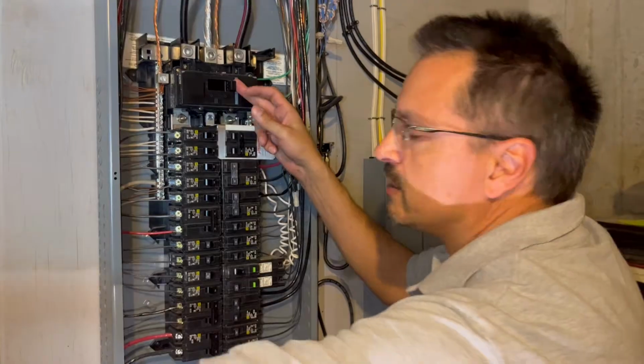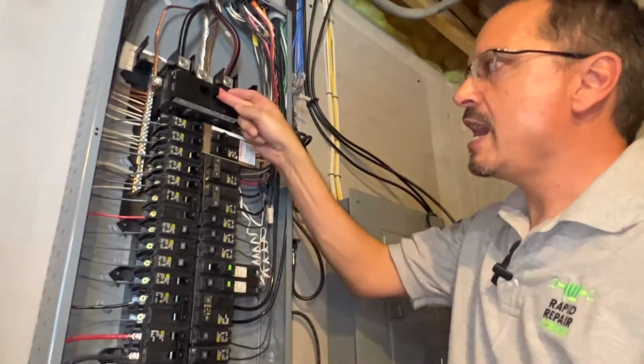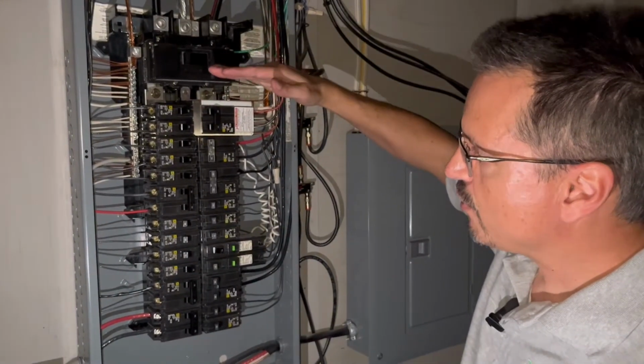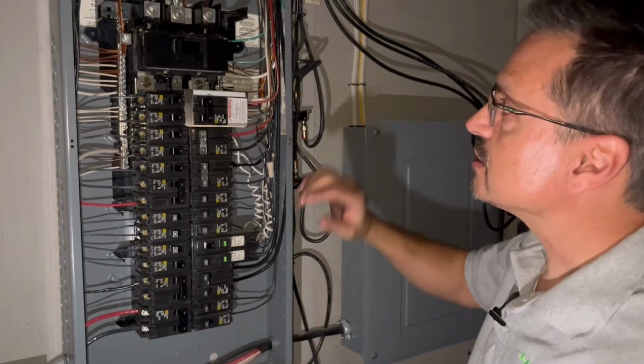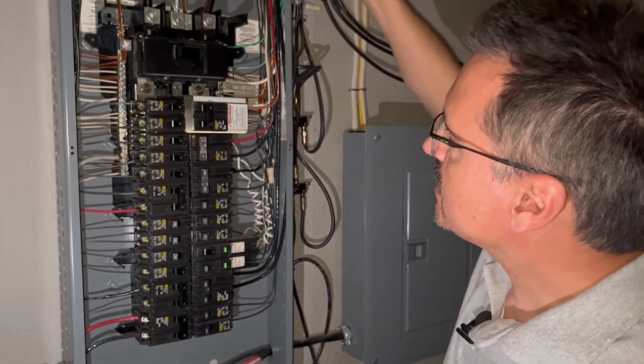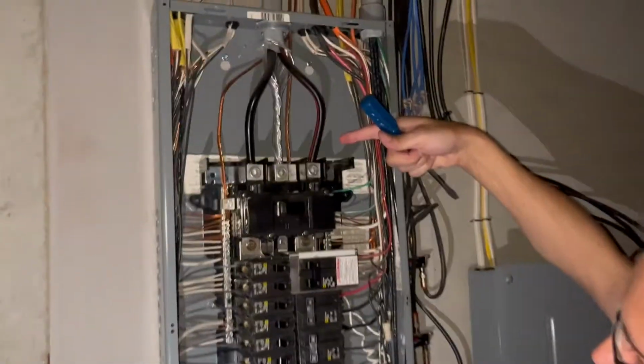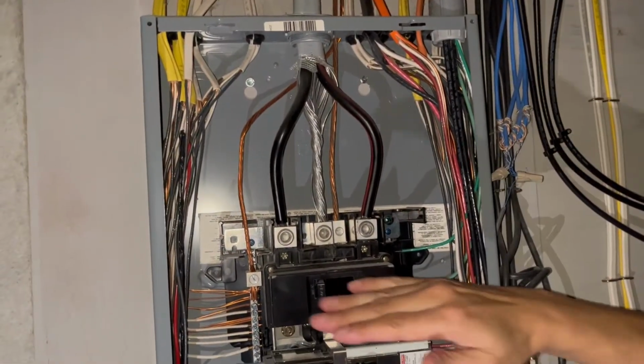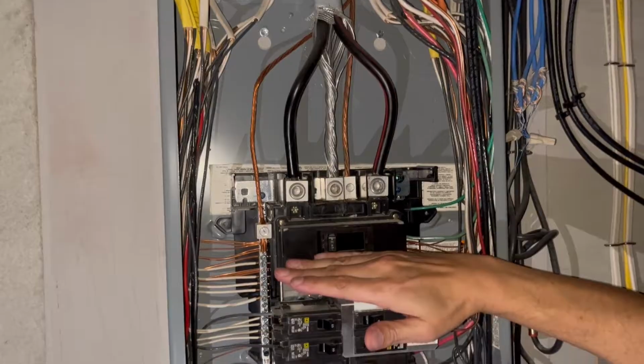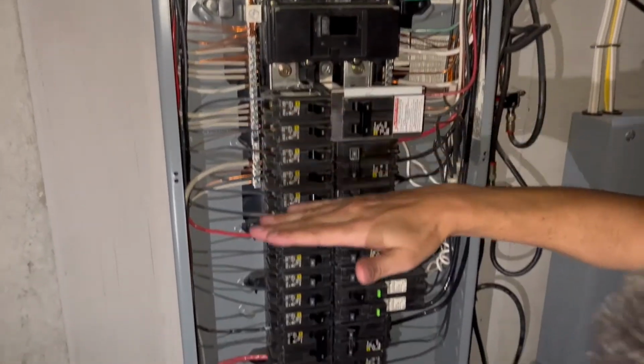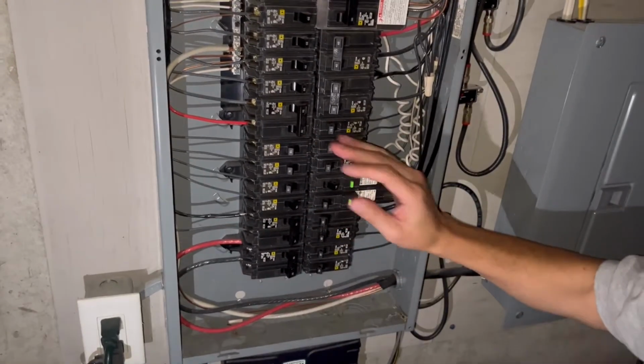Okay, so in this panel with the main disconnect at the top, I turn that off and everything beneath that is off, guys. Now, these conductors up here are still live. These black conductors from the utility company are still live. You don't want to touch anything above there. This is your main disconnect. We've turned that off. So now everything beneath that is off and we can work on the panel.